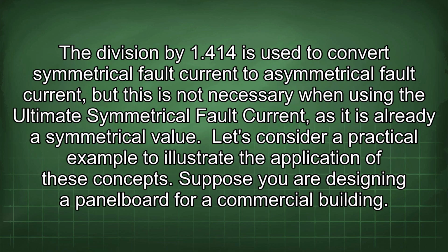The division by 1.414 is used to convert symmetrical fault current to asymmetrical fault current, but this is not necessary when using the ultimate symmetrical fault current, as it is already a symmetrical value. Let's consider a practical example to illustrate the application of these concepts.